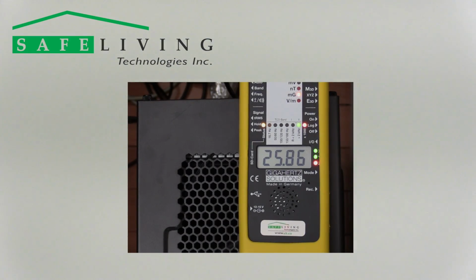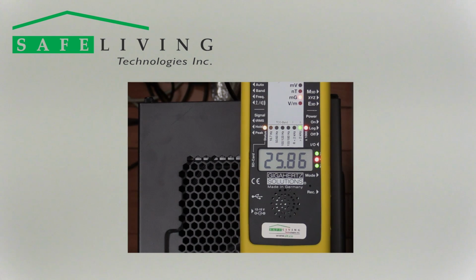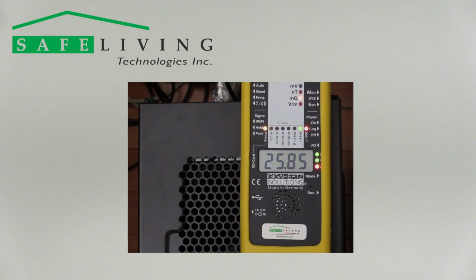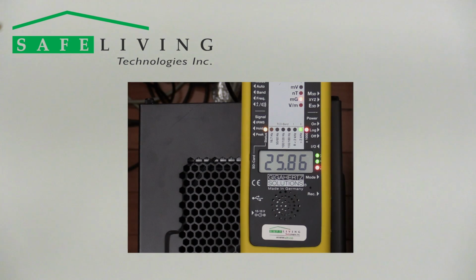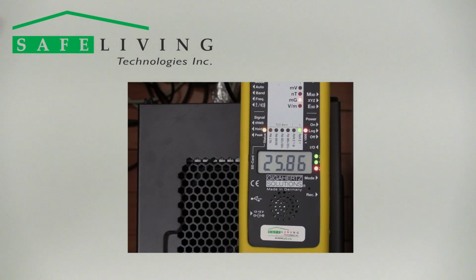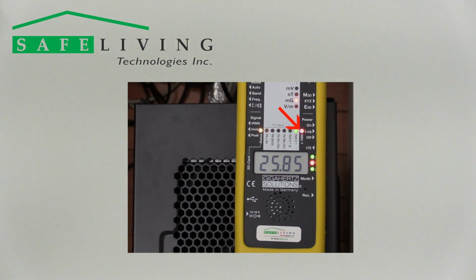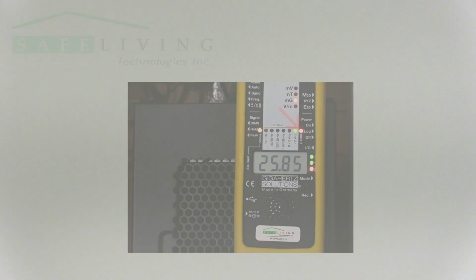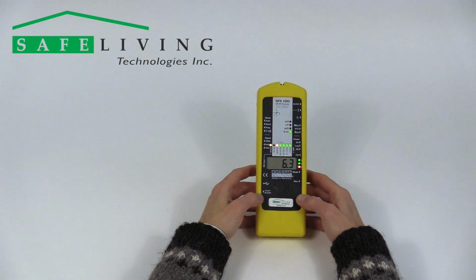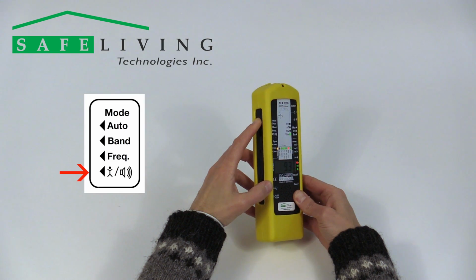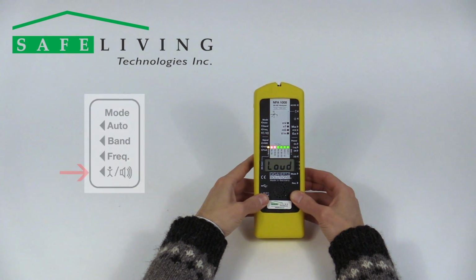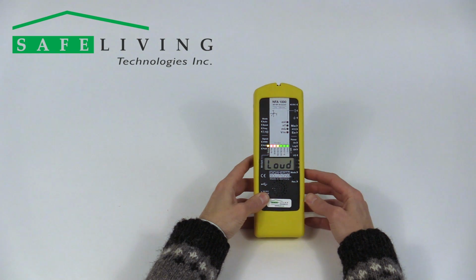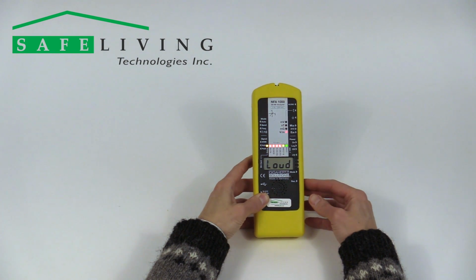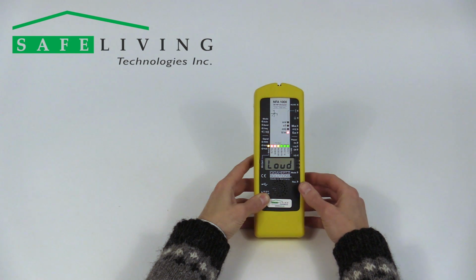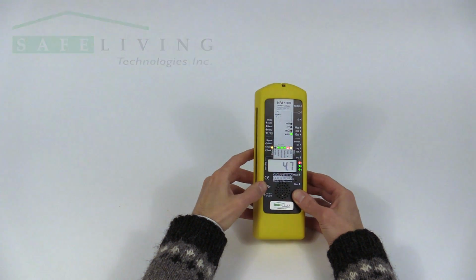Here is an example of a switching power supply in frequency mode. In this case, we have set the meter to display 3D magnetic fields over 2 kHz. The display is showing a frequency of just under 26,000 Hz, that is 25.86, multiplied by 1,000 as indicated by this red LED. To change the volume level of the Geiger sound clicks, move the mode switch into its lowest position as shown. Simply use the mode and record buttons as shown to increase or decrease the volume as desired. When the volume is set to your liking, return the mode switch to its previous position.